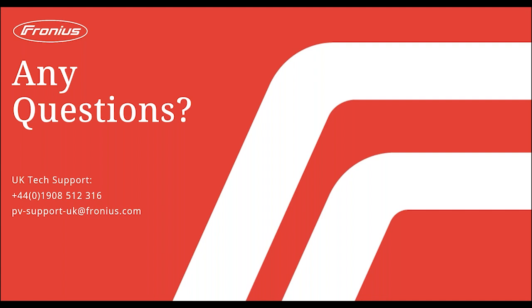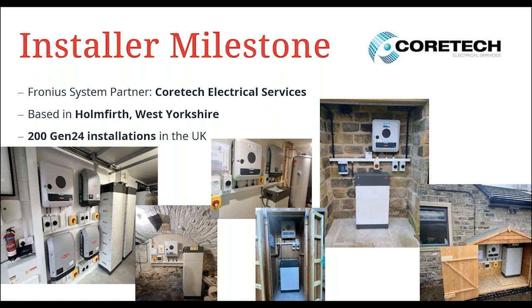Okay, thank you. Richard is asking, can Symo Gen24 couple with Snap inverters? So yes, we can have a Gen24 and a Snap inverter on the same site, and I think we saw from Coretech they've done this a number of times. The very first photo you see on the screen now shows one Gen24 with all those batteries connected, 2 stacks of batteries, and then 3 Snap inverters in this instance. And that Gen24 is drawing the surplus energy from all those other inverters, and able to dump that into the battery. So yes, you can certainly mix and match. And with the firmware update, you'll also be able to do the export limitation of those Snap inverters as well.